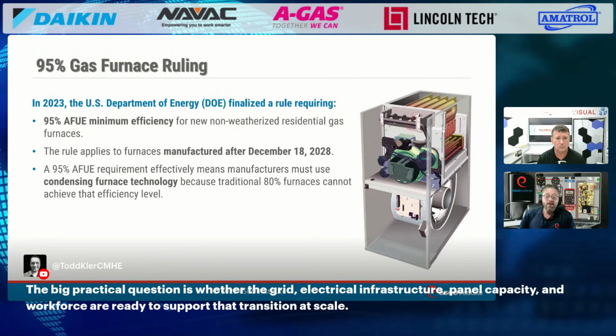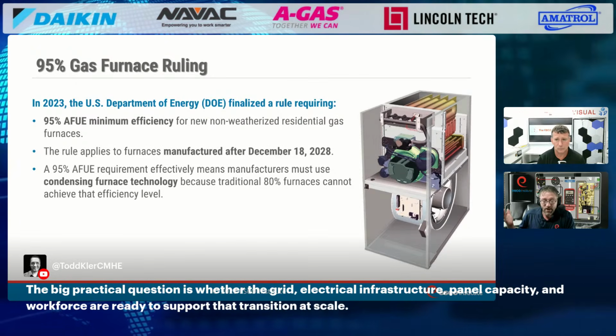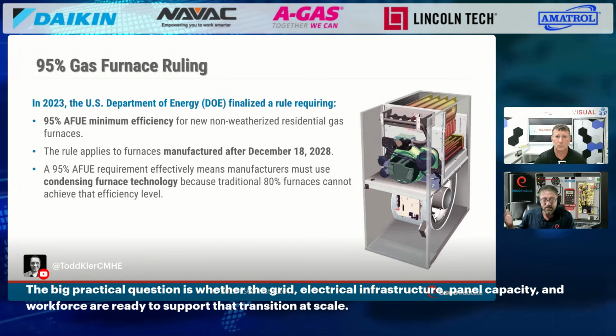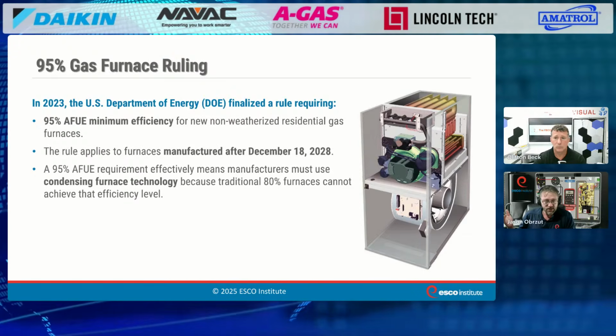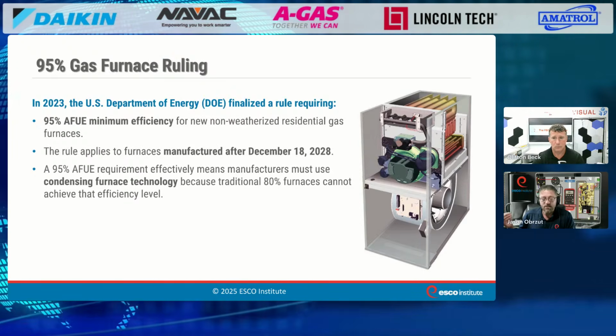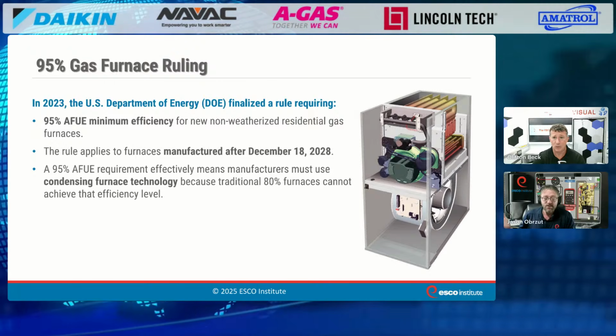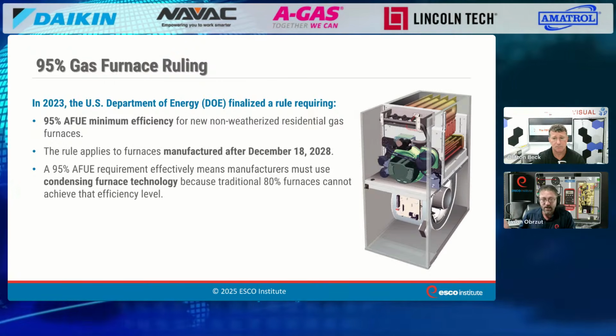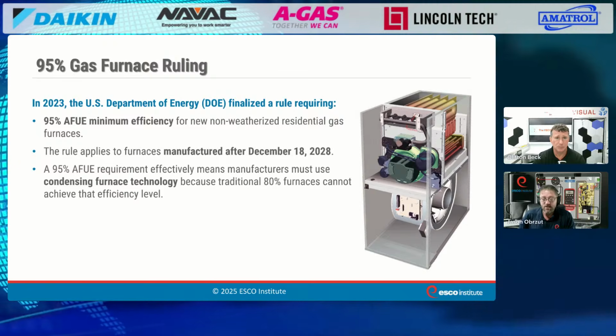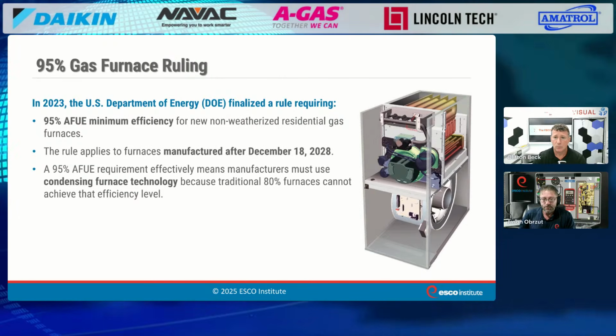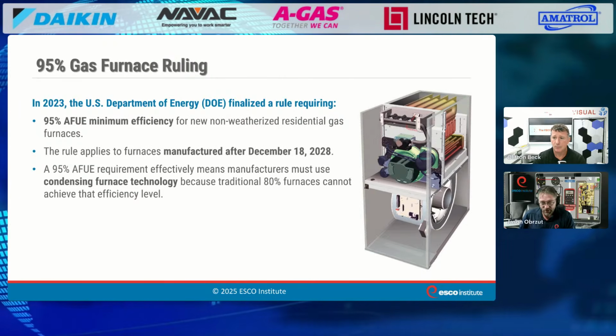So what do you do where we are, up in the Midwest, with freezing temperatures and attic installations, where you can't put a condensing furnace in an attic because it's an unconditioned space? Your trap will freeze, your secondary heat exchanger will freeze from the moisture. What do you do? Well, you've got to go to a heat pump or electric heat.